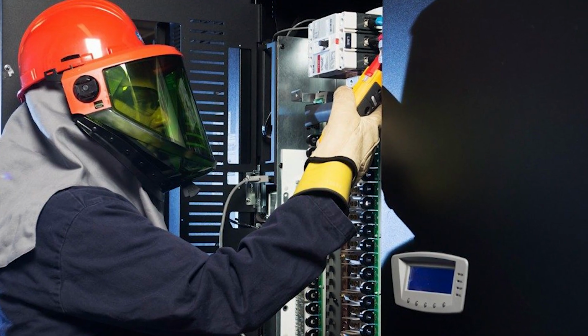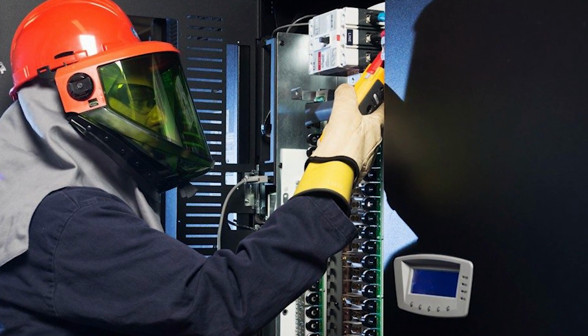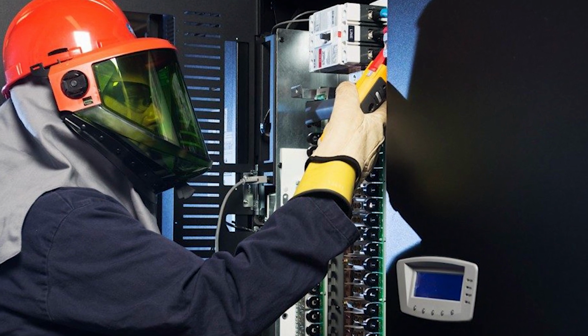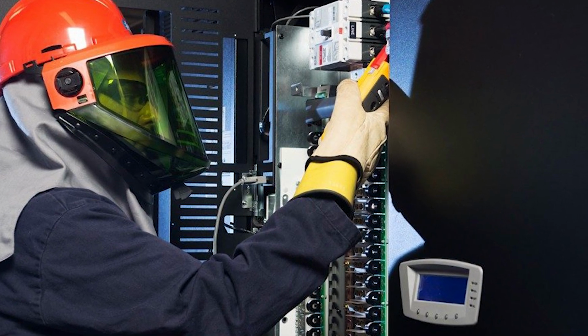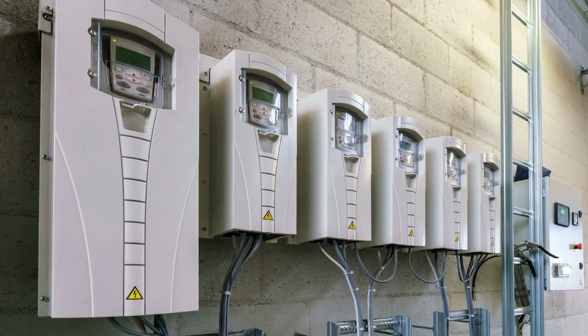What is a UPS? Now, why a UPS is the next question people ask. A UPS is used for insurance purposes. It prevents you from taking a big loss when something happens with the power. Especially with the double conversion, it takes all the crazy stuff out of the power, like harmonics. If you have a lot of variable speed drives in your facility, they create a lot of harmonics that come back in and can corrupt the clean sine wave. And it can affect certain equipment that is sensitive.